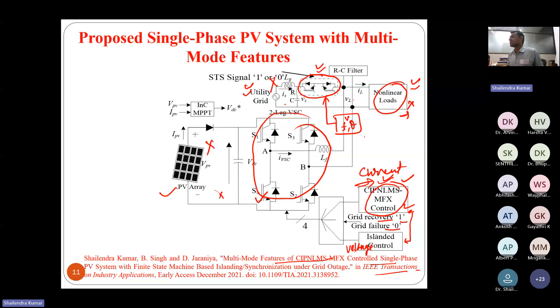So if you talk about this system, if grid and PV both are not available—suppose grid is not available, solar is not available, and grid is also not available—this emergency load cannot be supplied. This system will be shut down in that condition. So what we have done, we have connected a backup to these systems. So when PV and grid both are not there, these dynamic conditions we have tested in hardware as well. If grid utility and PV array both are not there, in that case battery will be discharged through this mode.